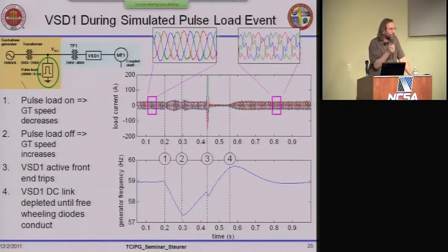The pulse is gone, and at this point something happens. You see a transient occurring, the current essentially goes away, and then all of a sudden we see very distorted currents from that variable speed drive. What happened is that the phase-locked loop of the variable speed drive couldn't keep up with the frequency increase and stopped firing the active front end, and the diode rectifier stayed on.